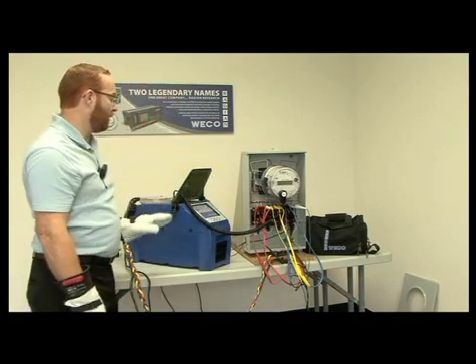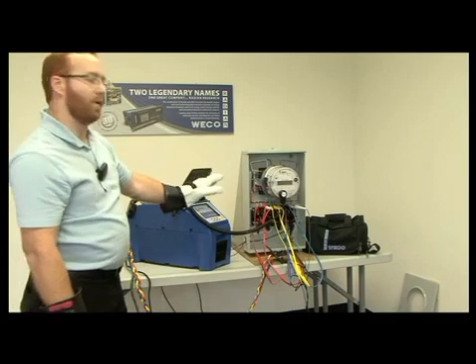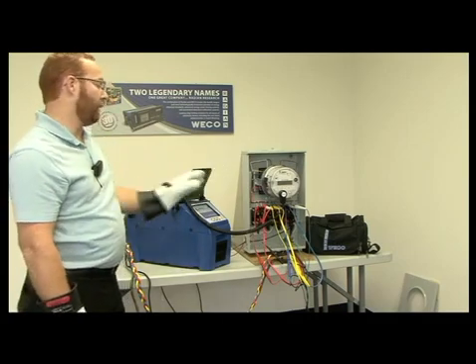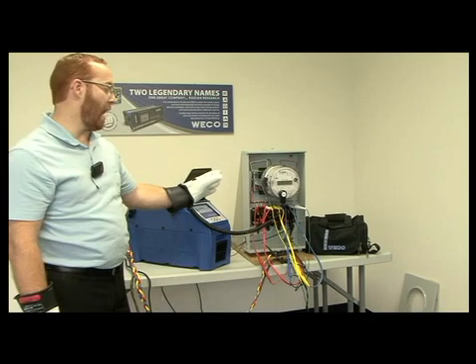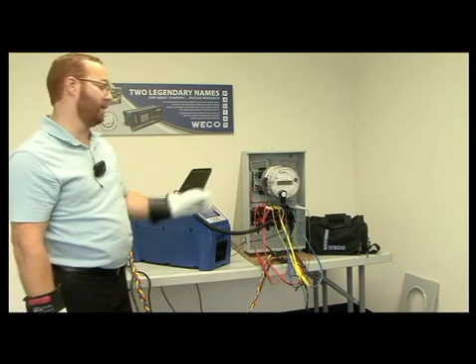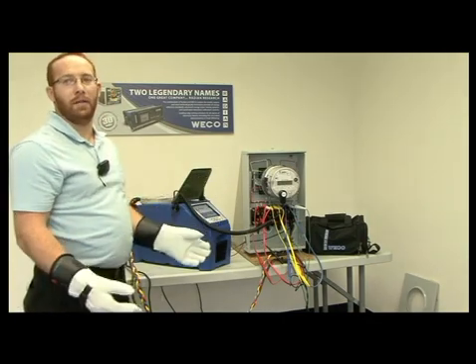Now the Bantam Plus will energize the meter with 120 volts on each phase. It will energize current at 2.5 amps for full load on each phase. And that will be at unity power factor.